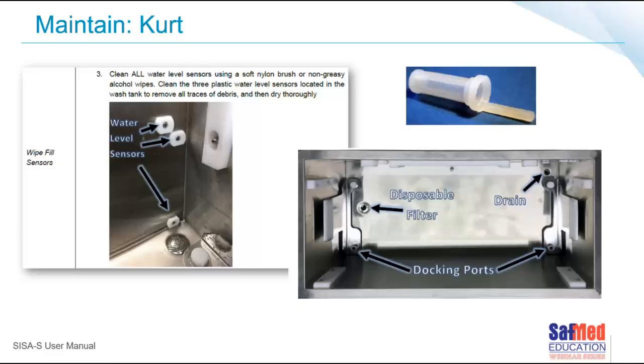So just to understand, of course, this is now when we're dealing with an automated system. So here we put the instruments in, right? We press the button, and the cycle begins, and the bath actually fills up. Those sensors will now tell the machine when to stop filling because now it's full. We don't need any water. If there's an error or an issue, and for some reason it fills up a bit too much, then there's another sensor to protect that. If it's really going even beyond those sensors for some unknown reason, it actually all drains out through the overflow. That's correct. So that's the final safety feature, and you won't have any spillage on your floor in the CSSD.